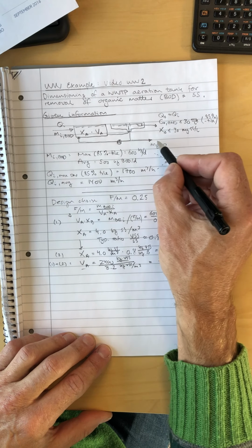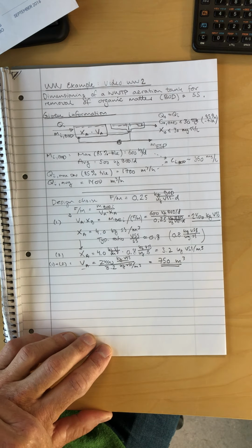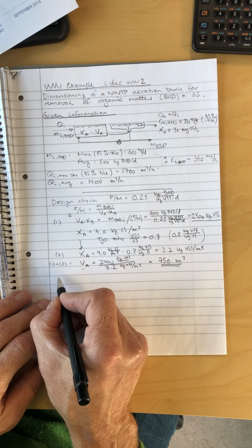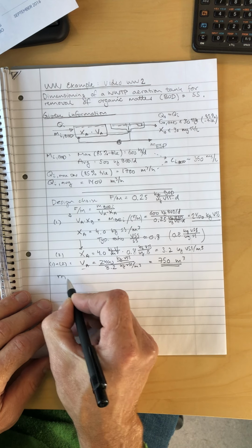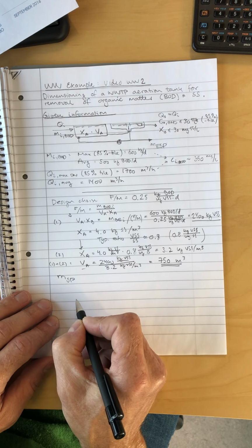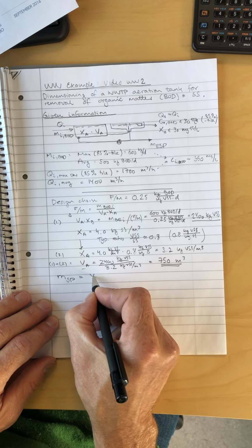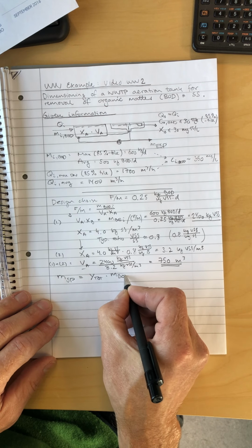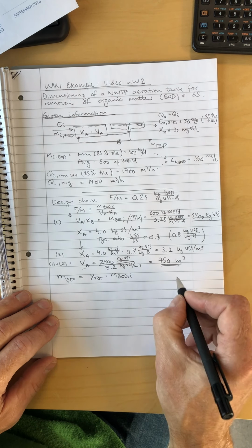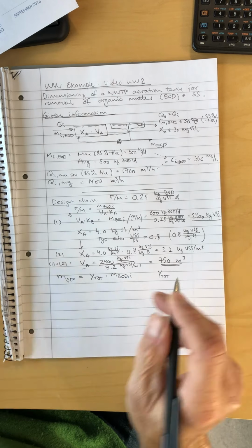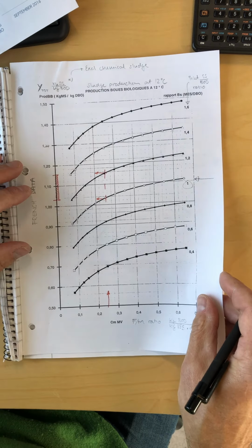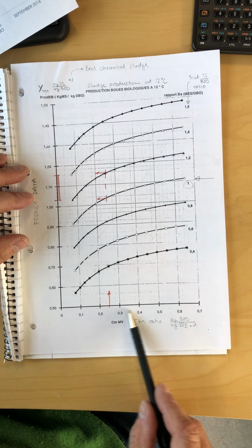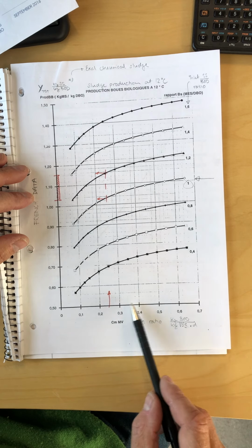Could be interesting to see how much sludge I am going to deal with, so calculating the mass of excess sludge production. The easiest way forward is to calculate the mass of the total sludge production, which is equal to the yield constant times the mass of BOD in the inlet. A yield constant for a plant like this, I need to go to the literature to get some heuristics. That could be this scheme here, where I've got the FM ratio for these medium loaded plants.